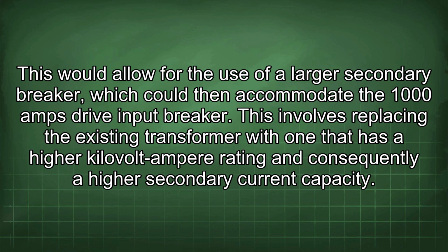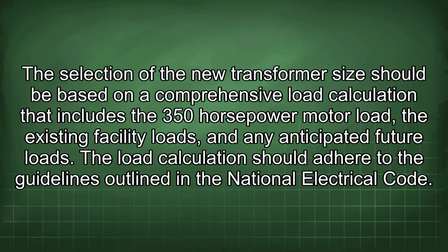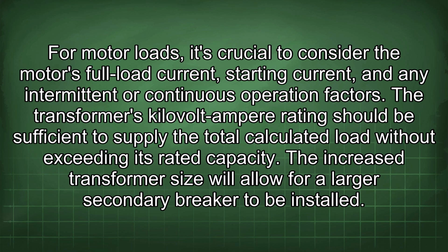current capacity. The selection of the new transformer size should be based on a comprehensive load calculation that includes the 350 horsepower motor load, the existing facility loads, and any anticipated future loads. The load calculation should adhere to the guidelines outlined in the National Electrical Code. For motor loads, it's crucial to consider the motor's full load current, starting current, and any intermittent or continuous operation factors. The transformer's kilovolt ampere rating should be sufficient to supply the total calculated load without exceeding its rated capacity.